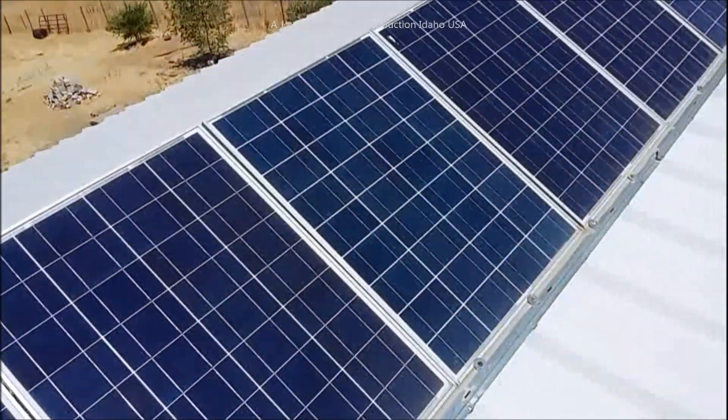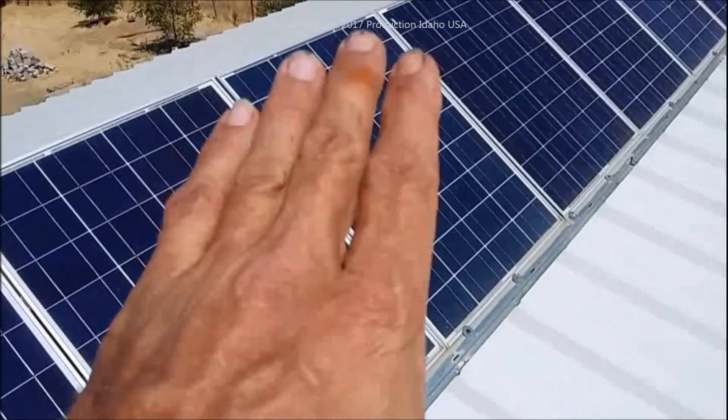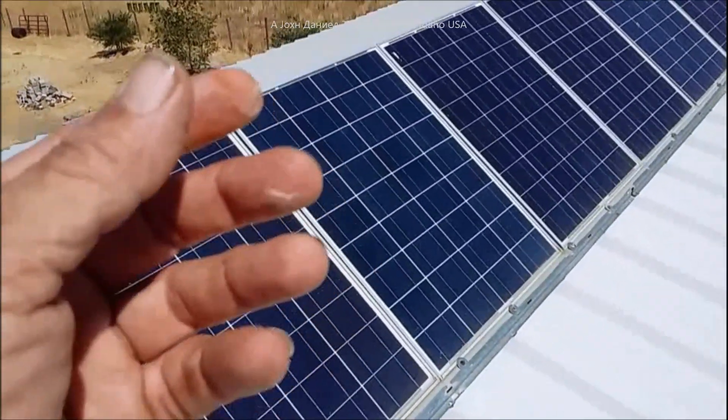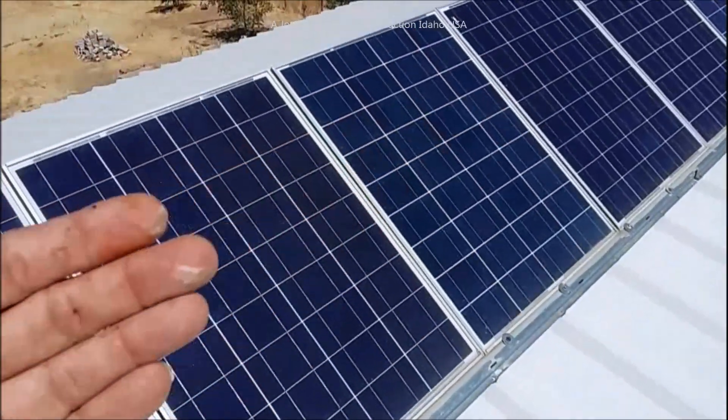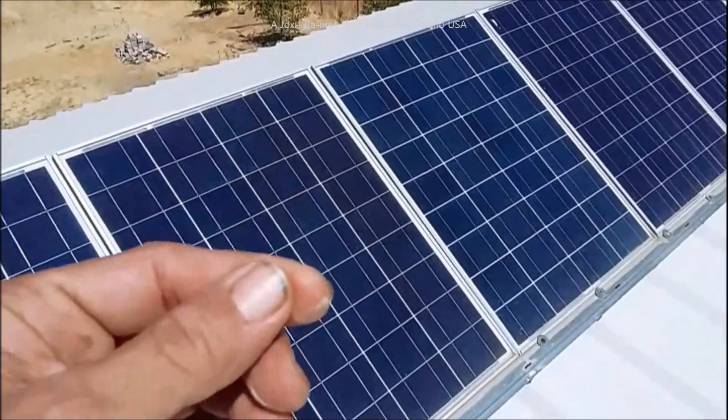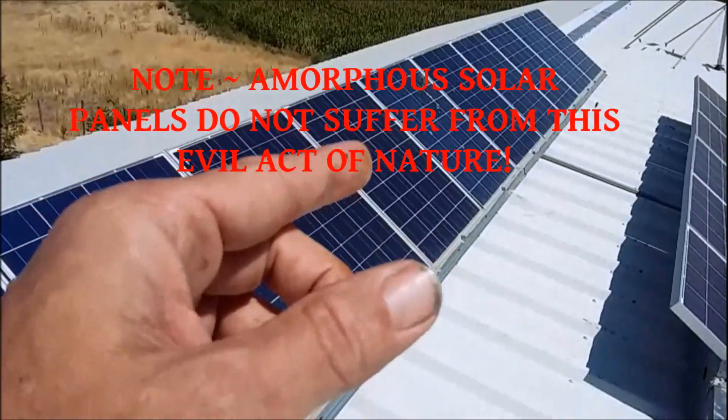That 45 watt panel burned out. It got excessively dirty and got a lot of bird shit on it. And what happened is the other panels pushed against its diodes. So instead of the panel being damaged, it was the diode that failed.